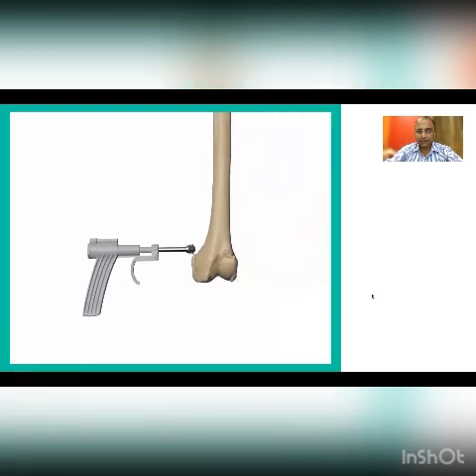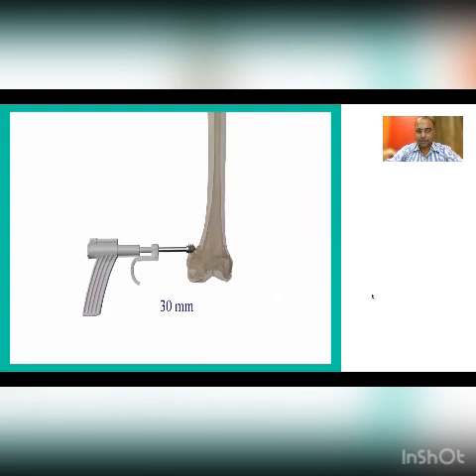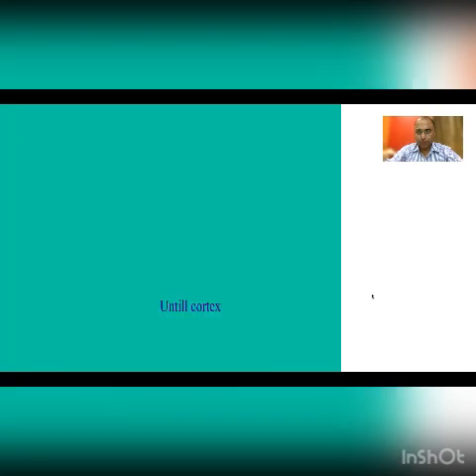Next, we will see the use of an intelligent bone biopsy device. The needle has specific sensors including depth, distance, and pressure sensors. It can be calibrated according to the disease of the bone, and the device will stop automatically at the opposite cortex of the tumor.